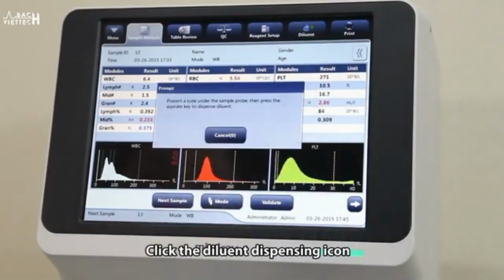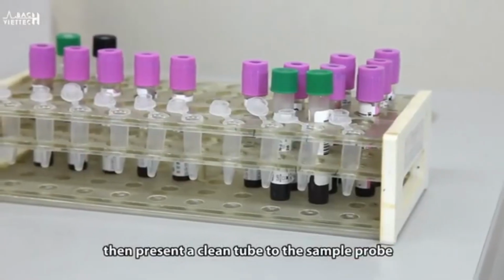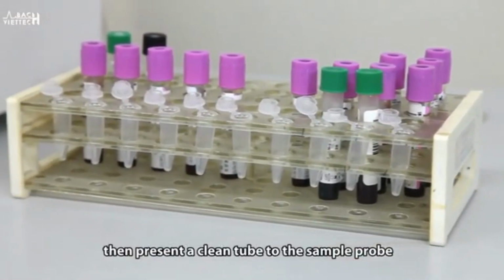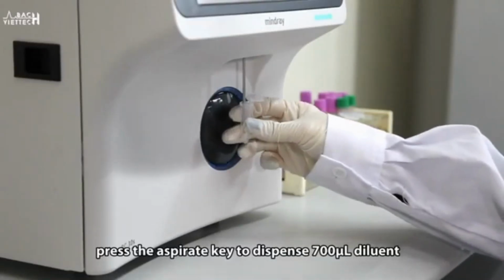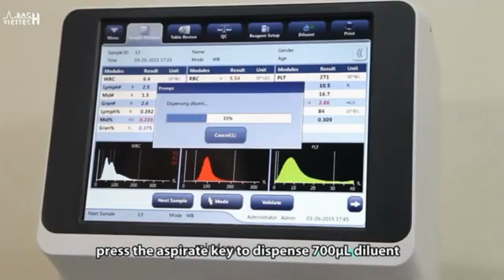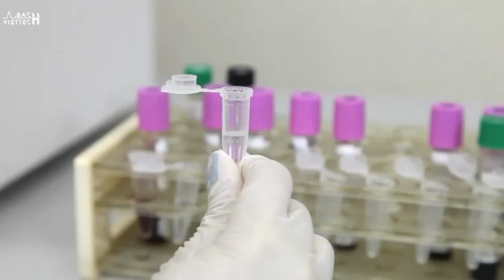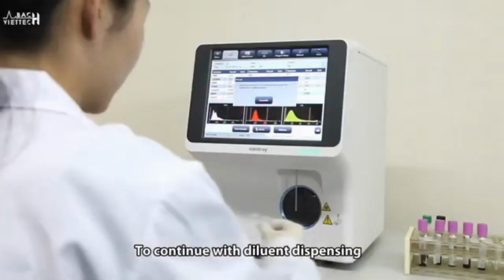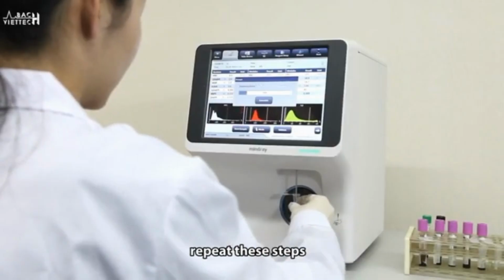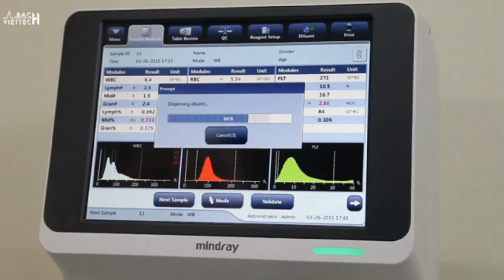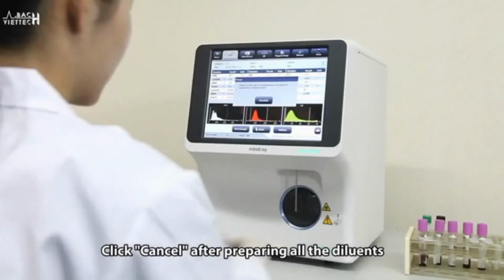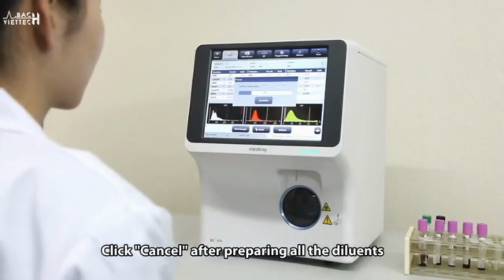Click the diluent dispensing icon, then present a clean tube to the sample probe. Press the aspirate key to dispense 700 microliters diluent. To continue with diluent dispensing, repeat these steps. Click Cancel after preparing all the diluents.